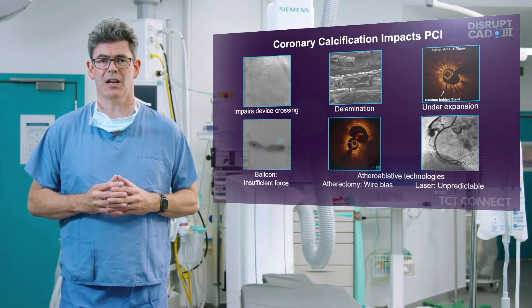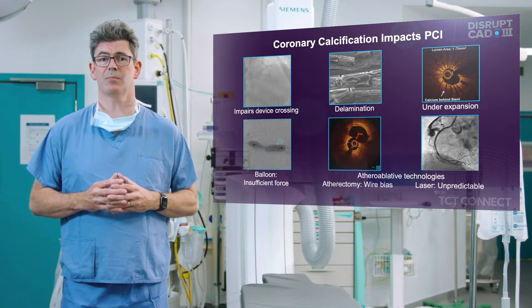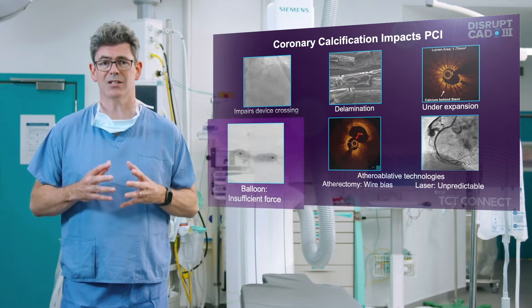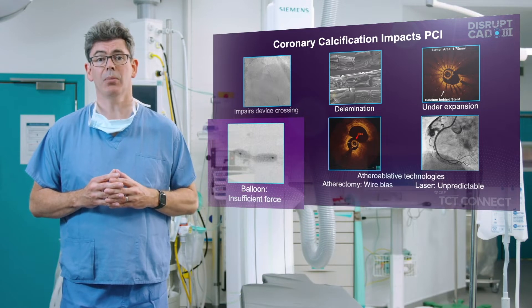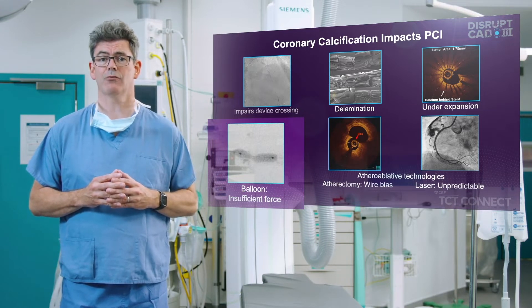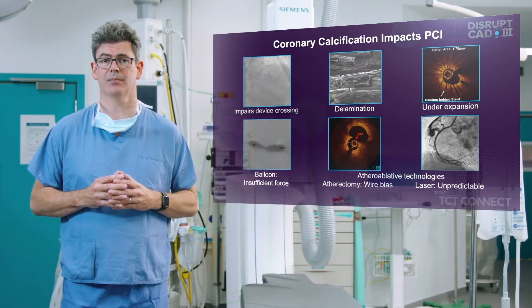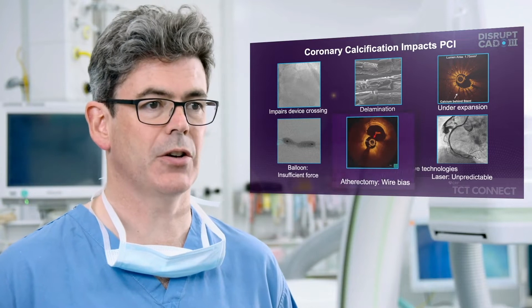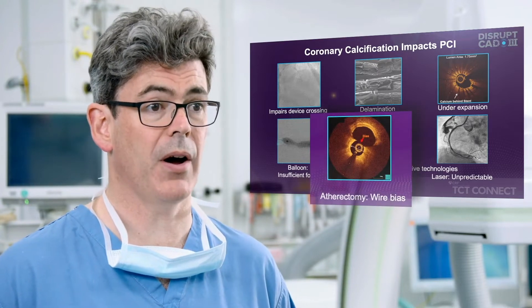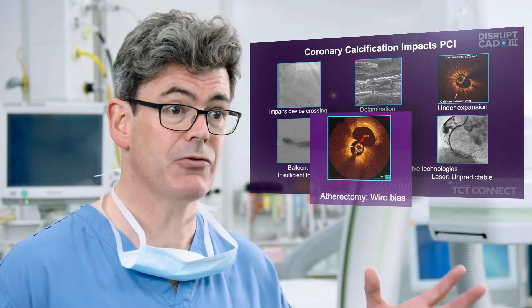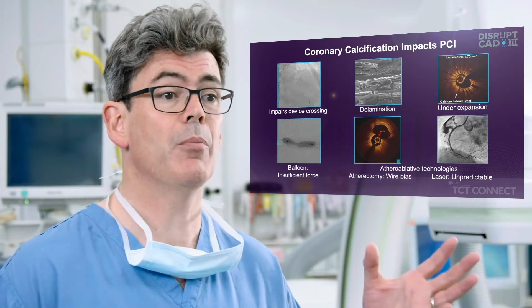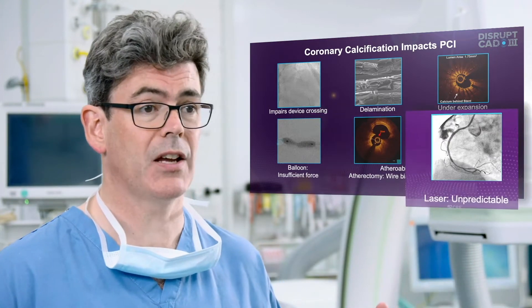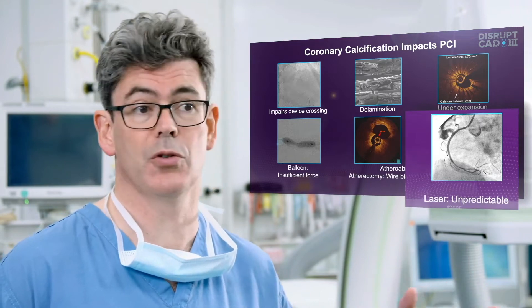Current technologies are limited with respect to their ability to treat calcium. Balloons have insufficient force even at 20 to 30 atmospheres and are complicated by barotrauma and rupture. Atheroablative technologies are limited by wire bias in an eccentric rut or trough created by atherectomy, or unpredictable complications such as perforations caused by laser.